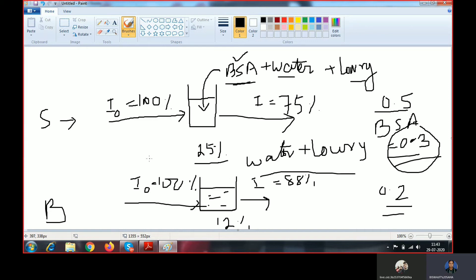Now say voltage is fluctuating. When we are getting the value of blank — say blank is 0.2 OD — and when we are transferring the sample into the spectrophotometer, the voltage actually fluctuates and decreases, so the OD value may differ. This is a basic problem in the single-beam spectrophotometer. Whenever you take the blank first and then take the sample, if voltage fluctuation occurs — either in the positive or negative direction — the OD value may also differ.